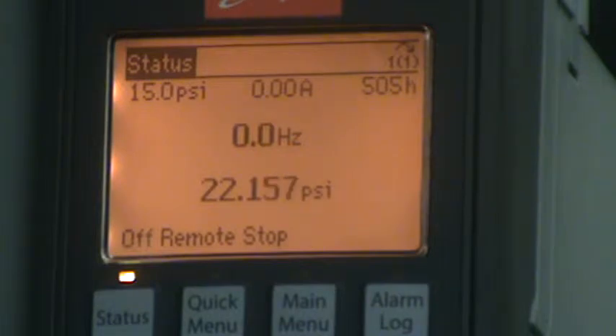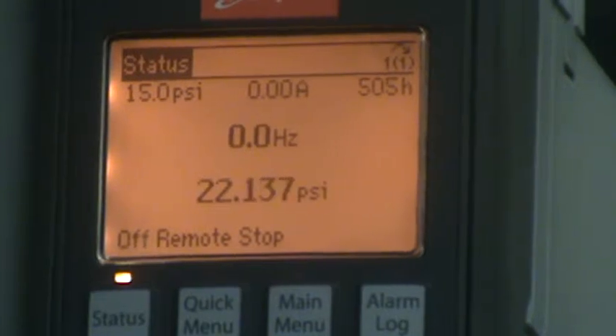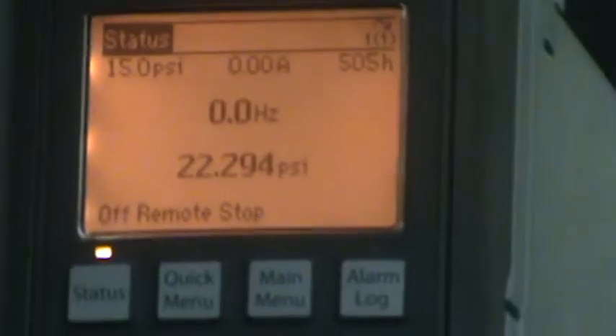Ramping means it's getting there, running means it's gotten there and it's happy. Okay. The other thing you can see is auto remote coast. That means something broke. Okay? The drive will sense that there's a problem with the motor and it fears that it will damage the motor or the drive. It will literally just electrically let go of the motor and just let it coast to a stop or let it coast to whatever's happening. And that's where you start to do some troubleshooting.